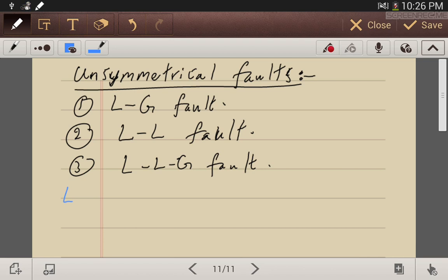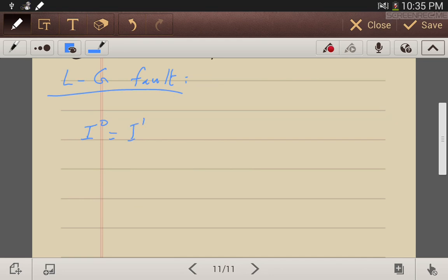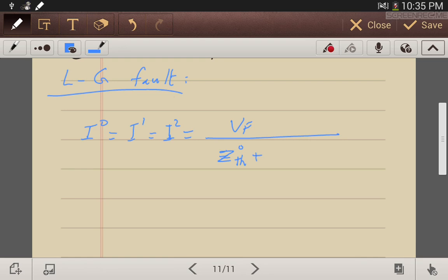For the single line-to-ground fault, I0 is equal to I1 is equal to I2, which is equal to the fault voltage divided by the Thevenin equivalent of the zero sequence impedance network, plus the Thevenin equivalent of the positive sequence network, plus the Thevenin of the negative sequence, plus 3Zf if there is a ground fault impedance.